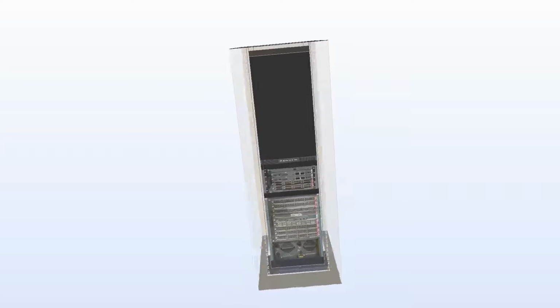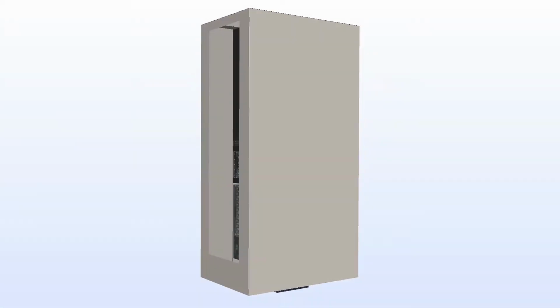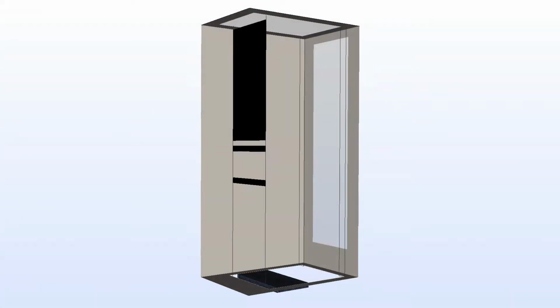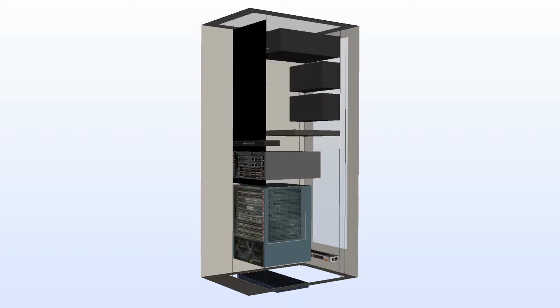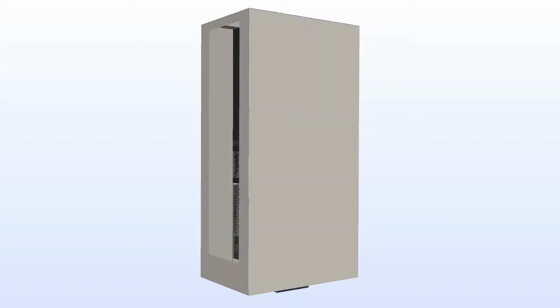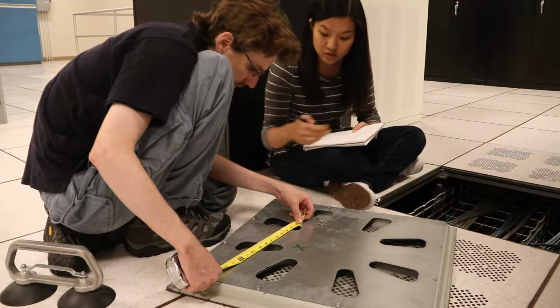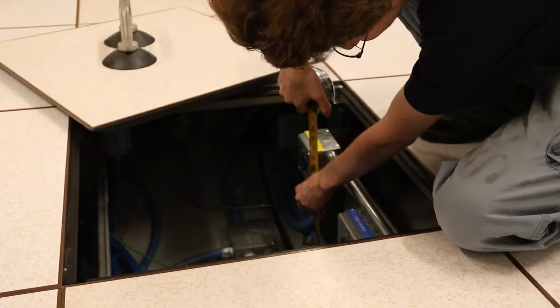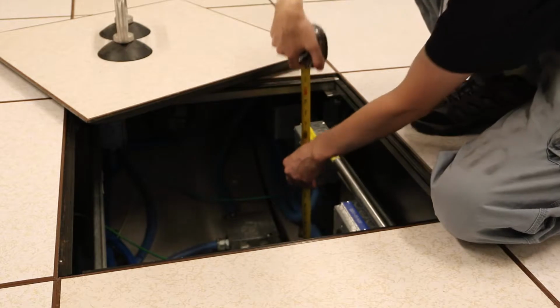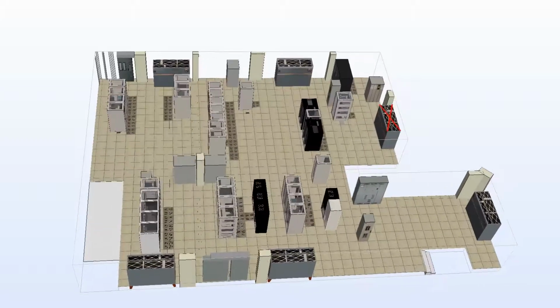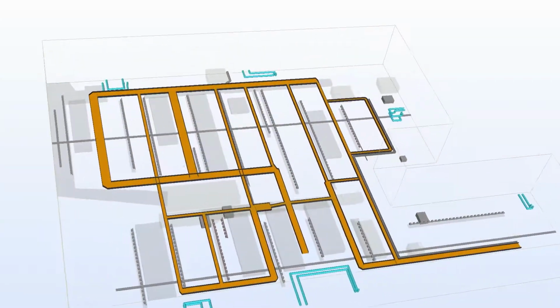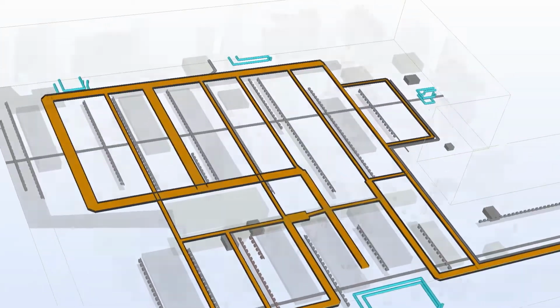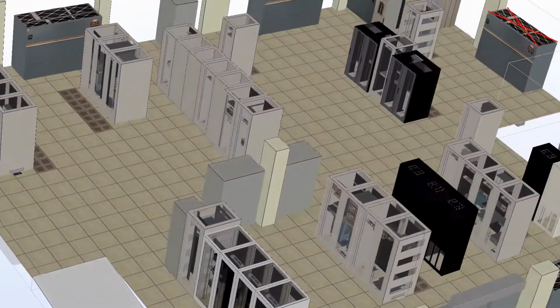This includes make, model, U-slot position, orientation, blanking, power connections, and any other objects found in the cabinets. This level of detail allows us to predict the inlet temperatures of each piece of IT. All major airflow blockages above and below the underfloor will also be accounted for in the model. These obstructions include chilled water piping, power conduits, network cables, beams, columns, PDU or CRAC substructures, and other miscellaneous items.